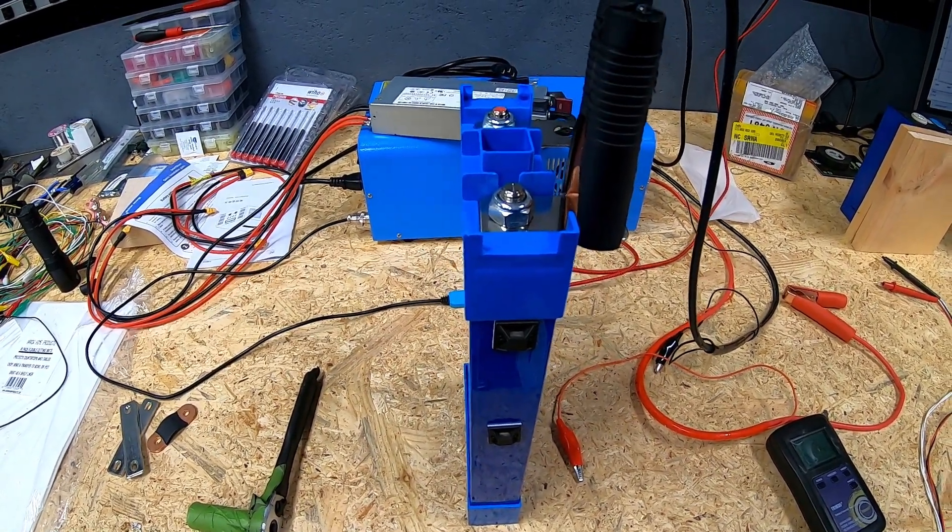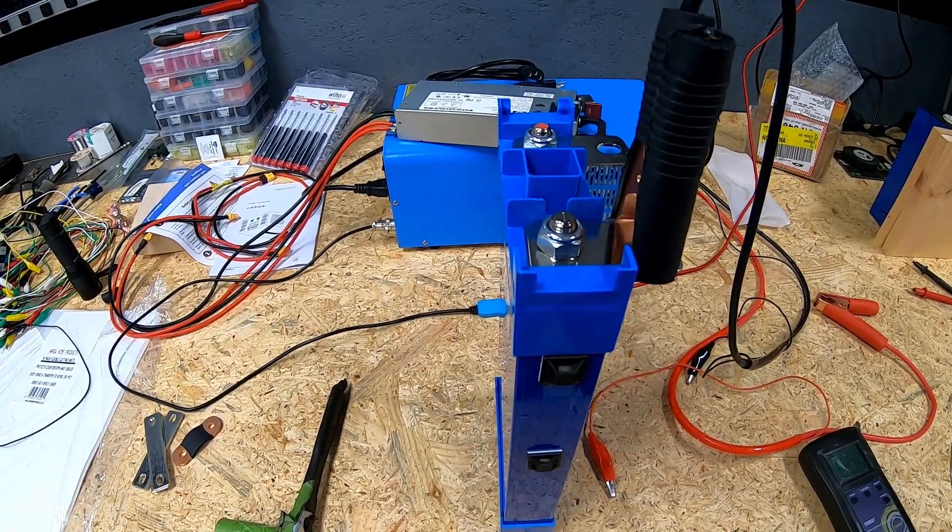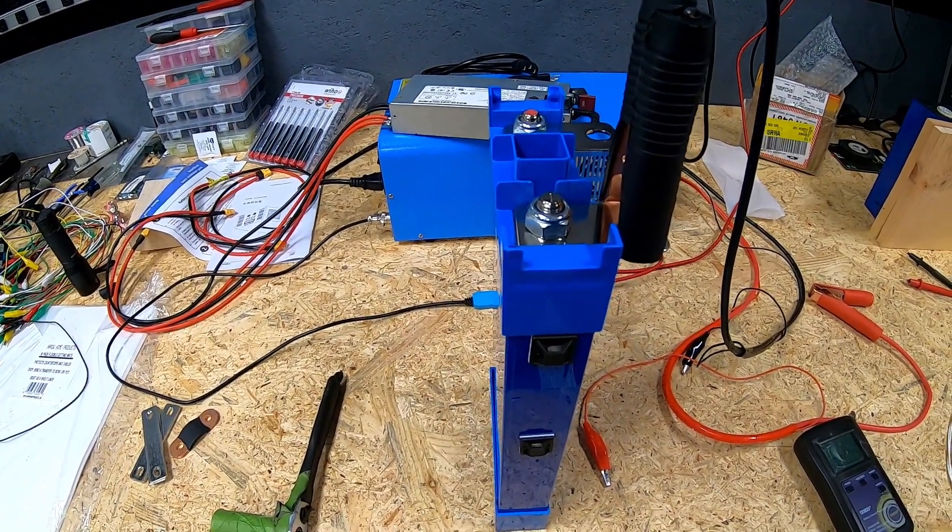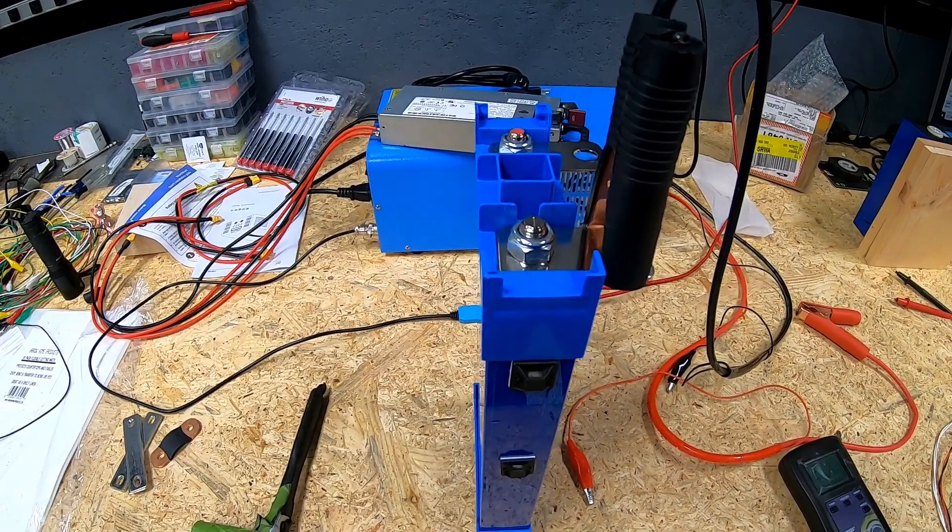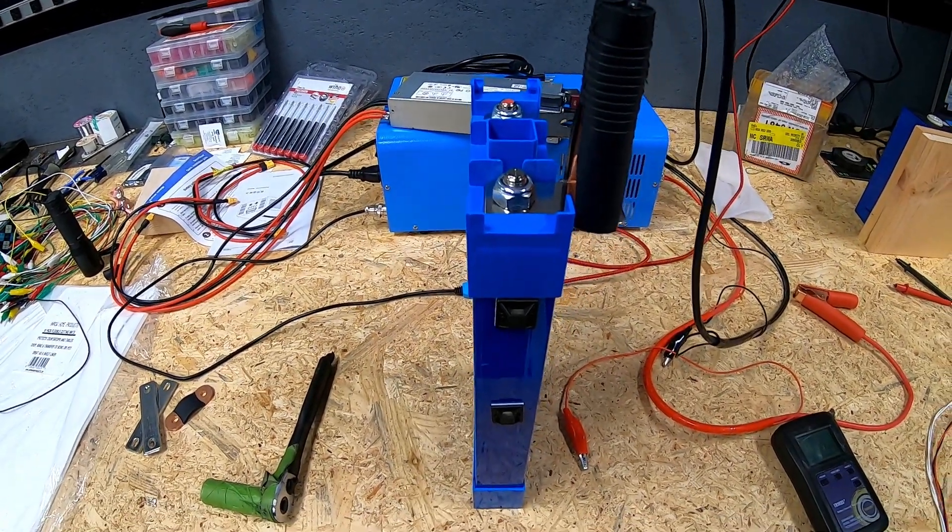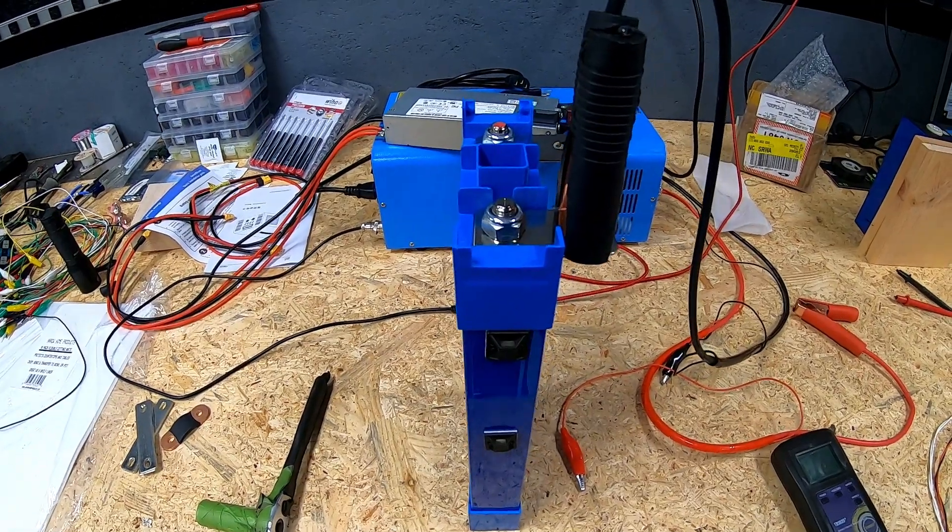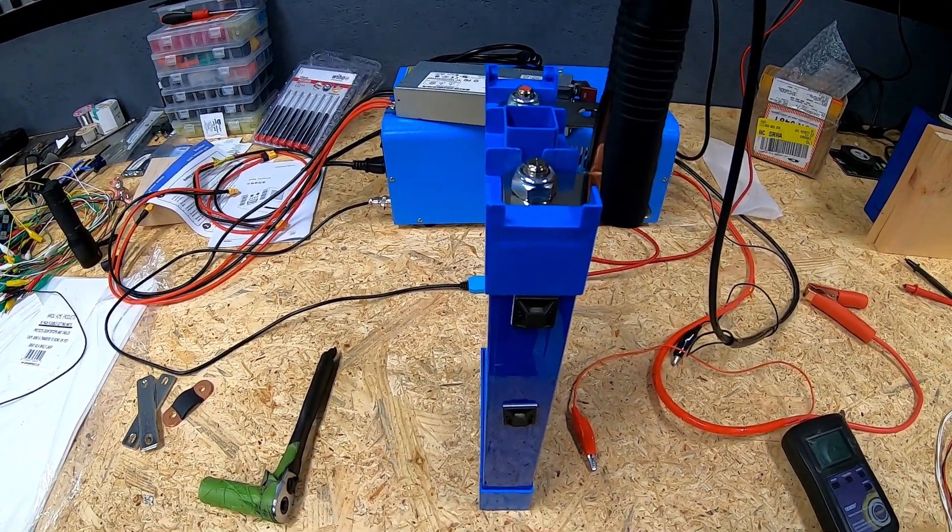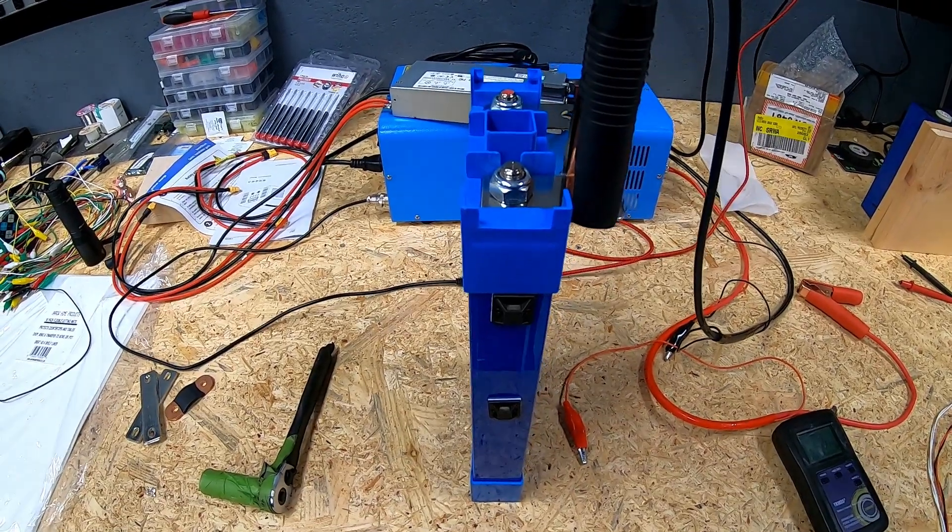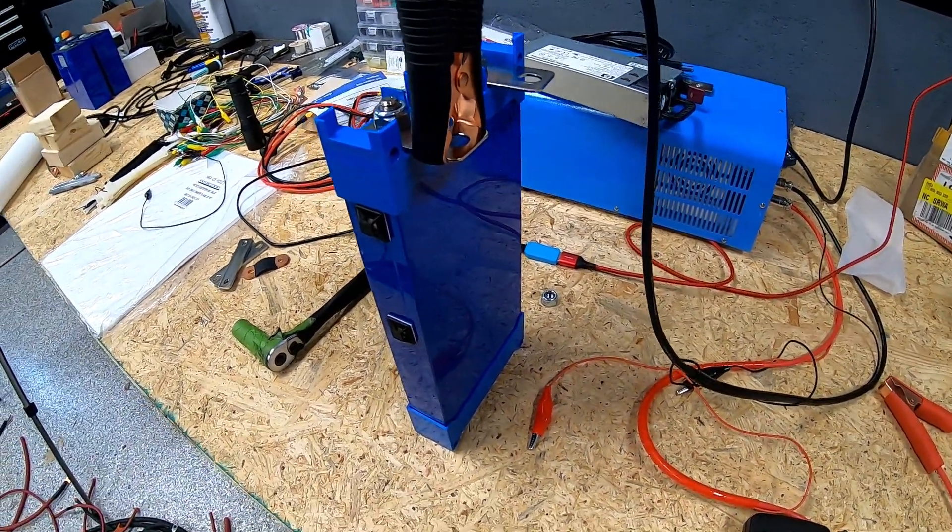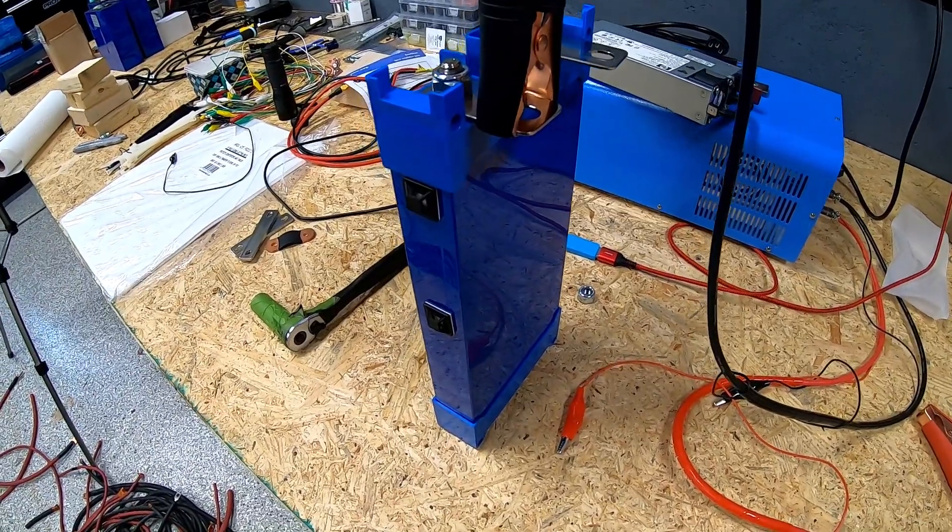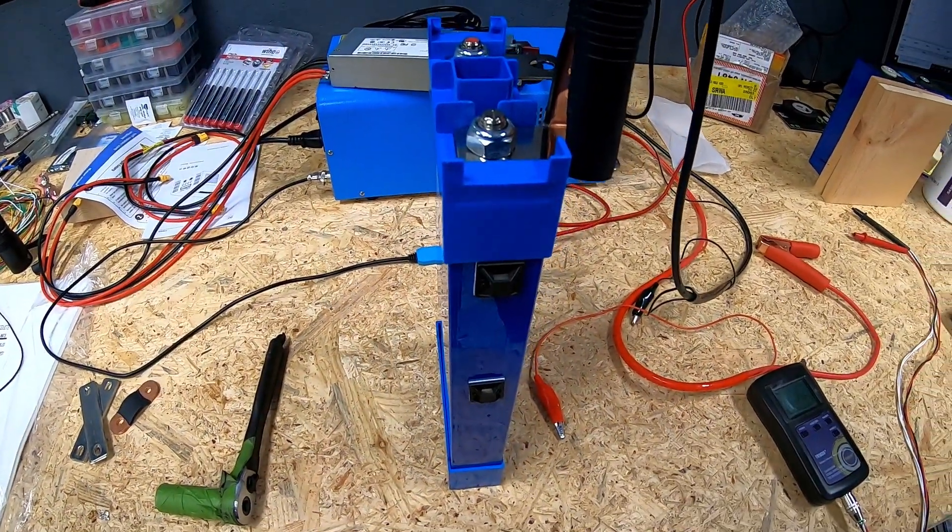What I figured we would do is take one of these very nice cells and do a charge test on it. This will tell us a couple of things: one, the Batrium software says the bank as a whole was at 50% state of charge when we shut it all down. Is this cell truly at a 50% state of charge?